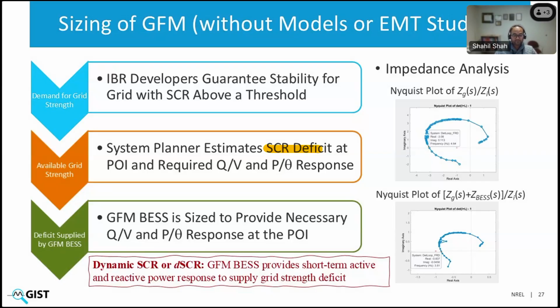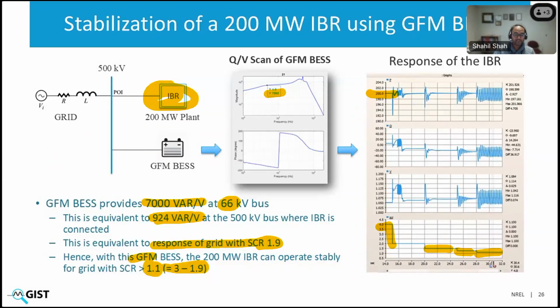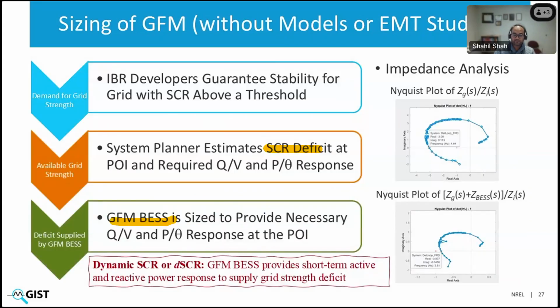And that drives how much grid forming BESS should be sized to achieve that Q by V or P by theta response. Now, in the previous slide, I said that this particular grid forming BESS is providing SCR of 1.9. I should be more exact. What I'm really trying to say is that it is providing short-term active and short-term reactive power response within that transient to subtransient time scale, so that it is behaving as if the grid strength in the dynamic sense is 1.9. So instead of calling it SCR contribution, because it's not really providing 1.9 per unit of short circuit currents, it is providing the short-term dynamic grid support. Maybe we can call this dynamic SCR or DSCR.